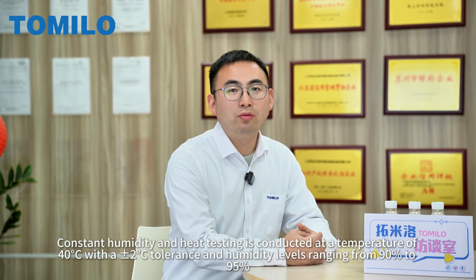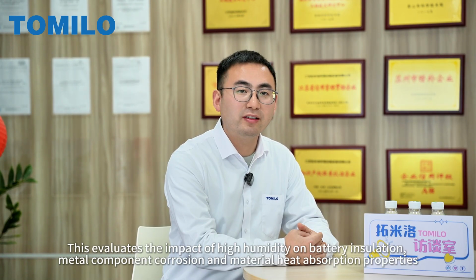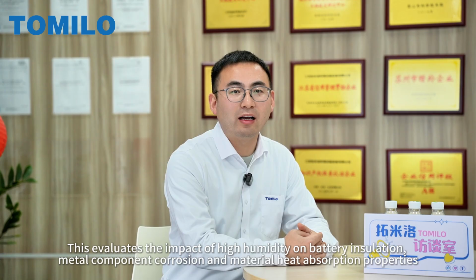Constant humidity and heat testing is conducted at a temperature of 40 degrees Celsius with a ±2 degrees Celsius tolerance and humidity levels ranging from 90% to 95%, lasting from 96 hours to 168 hours. This evaluates the impact of high humidity on battery insulation, metal component corrosion, and material heat absorption properties.